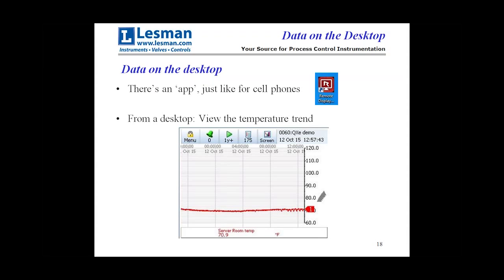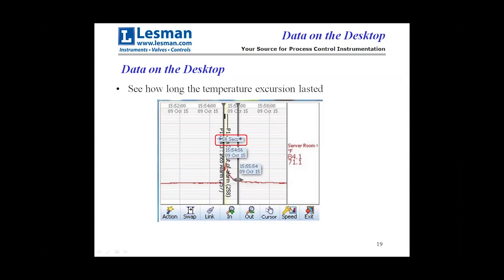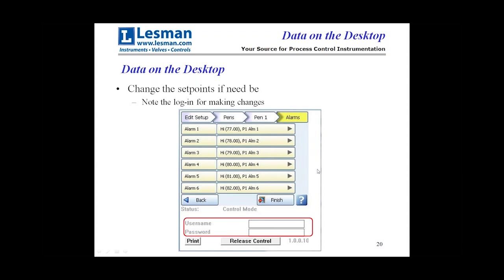We have a desktop app — a little icon — and from the desktop we can actually see the temperature trend, just like on a regular recorder. We can also see how long a temperature excursion lasted. For example, from one cursor point to another, it lasted only 58 seconds — that was just a test — and the temperature ranged from 71 to 84 degrees. We can go in and change those set points, viewing our six alarms and their various set points. Note that there's a login with username and password to make sure people don't get in and mess with it if they don't belong there.